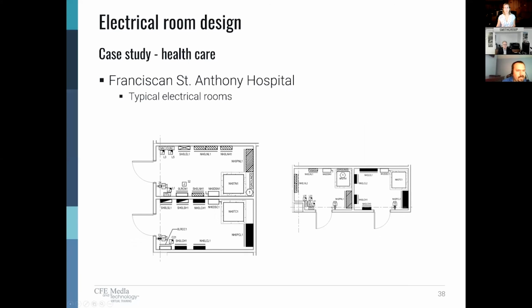And then I just wanted to give an example too of the typical electrical rooms that we saw on each floor that were stacked vertically to provide ease of conduit routing throughout the building. These were located close enough such that the 120 volt circuits that were coming out were limited to approximately 100 lineal feet to minimize voltage drop in the system. And you can see once again, now this isn't a code requirement, but it's a good practice to keep the essential system and the normal system equipment separated. So we had 2 separate closets in each area of the building.